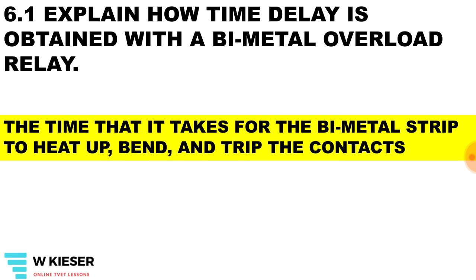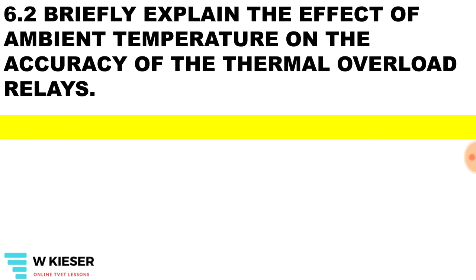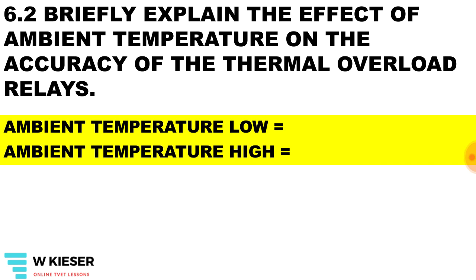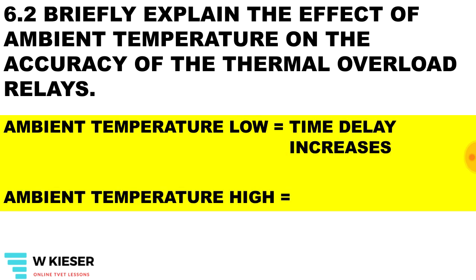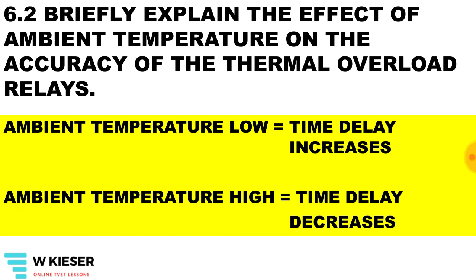Explain how time delay is obtained with a bi-metal overload relay. It is the time that it takes for the bi-metal strip to heat up, bend out of shape, and trip the contacts. Briefly explain the effects of ambient temperature on the accuracy of a thermal overload relay. Where the ambient temperature is low, the time delay increases. Where the ambient temperature is high, the time delay decreases.